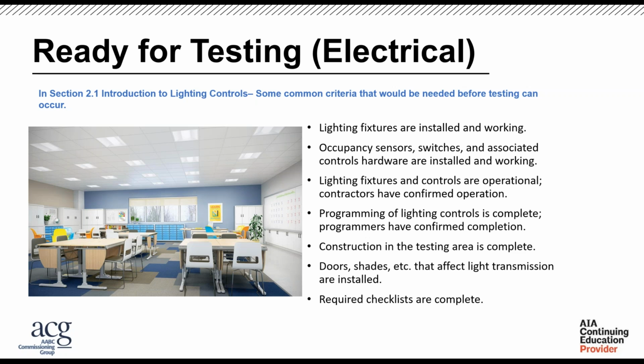You want to make sure the programming is done. A lot of times, and I understand for cost reasons, contractors tend to bring the lighting programmers in one time, so they want to wait until the end. However, if projects are phased, there are multiple testing opportunities, and we need to be cognizant of that. If you want to turn over a phase early, then at minimum that area needs to be programmed. And a big thing is that construction in that testing area is complete.